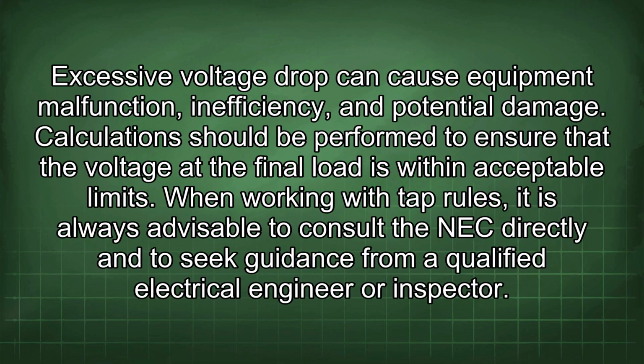Excessive voltage drop can cause equipment malfunction, inefficiency, and potential damage. Calculations should be performed to ensure that the voltage at the final load is within acceptable limits. When working with tap rules, it is always advisable to consult the NEC directly and to seek guidance from a qualified electrical engineer or inspector.